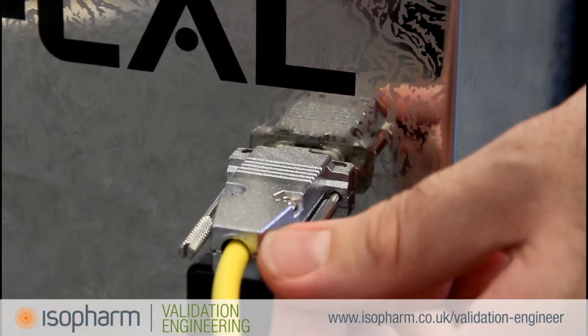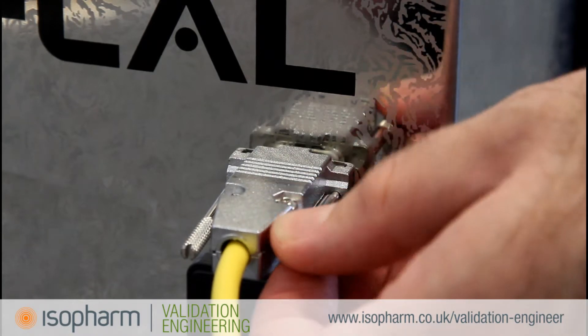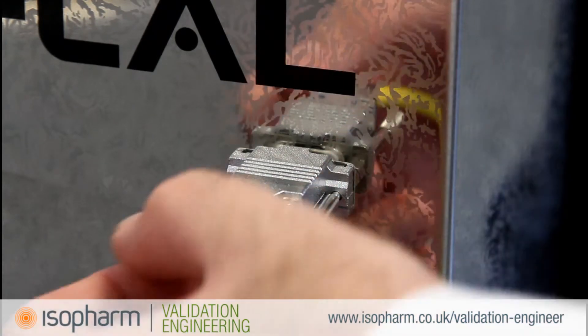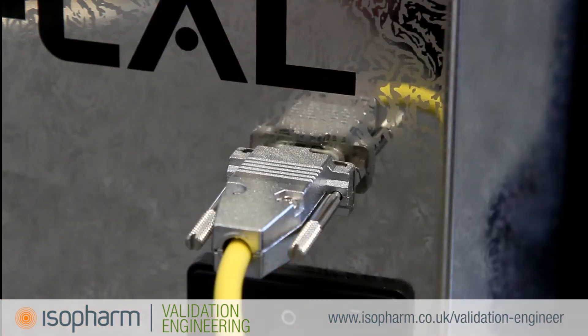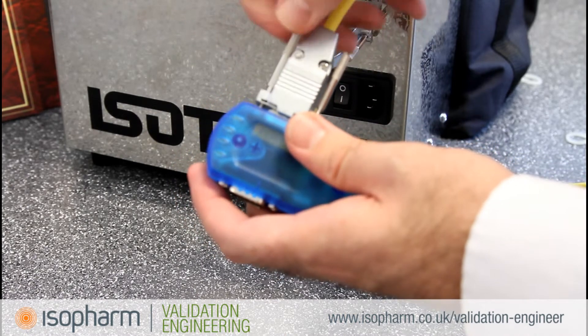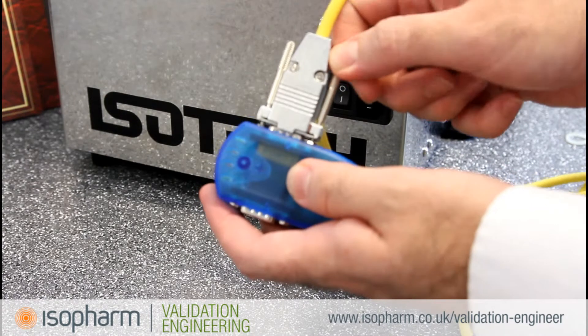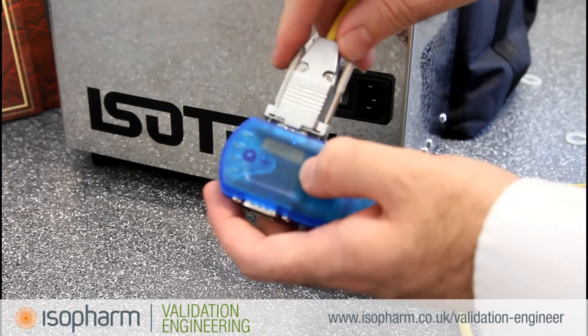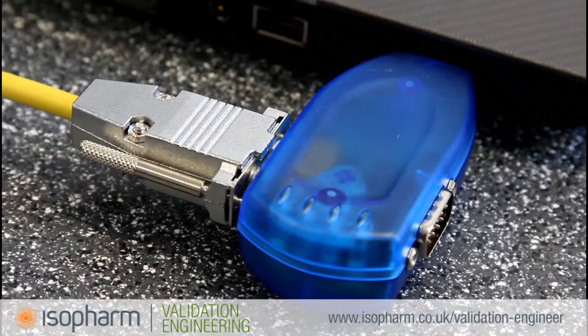If calibration is going to be done using the automatic calibration function in TQsoft, connect the heat reference unit to your PC using the RS232 connector and USB converter. The USB to serial converter is available separately from the Isopharm validation engineering shop.